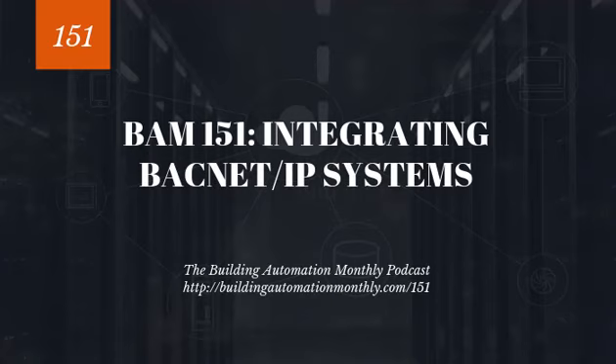So before I leave data, we're going to take our points list. We are going to understand what points we're mapping to. We're going to understand what priority we're mapping to. And we're going to understand what points correlate to points within the BAS. So the points on the lighting system, remember that whole space versus zone. We're going to consider that, and we're going to align our points back to the BAS system.